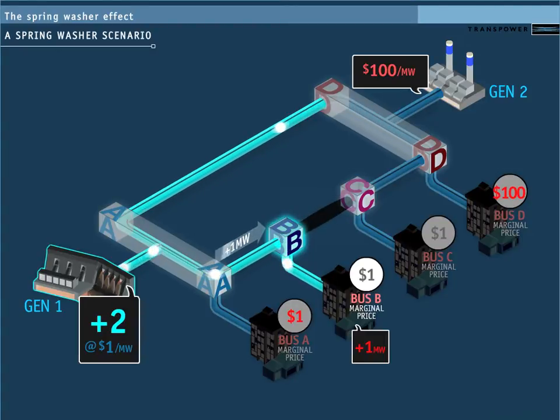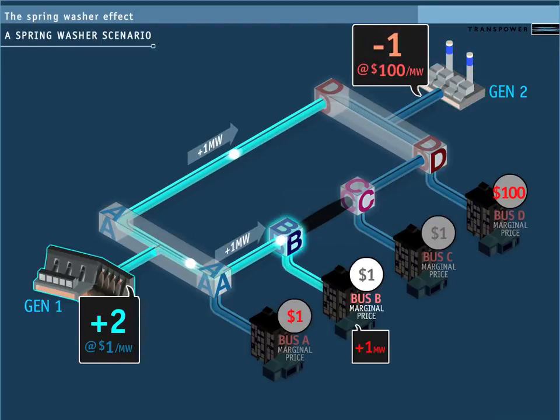Therefore, to get 1 megawatt to bus B, the generator would also have to send 1 megawatt along circuit AD. This would mean an extra unit of load is going to bus D. This would reduce the amount of generation required by generator 2 by 1 megawatt.